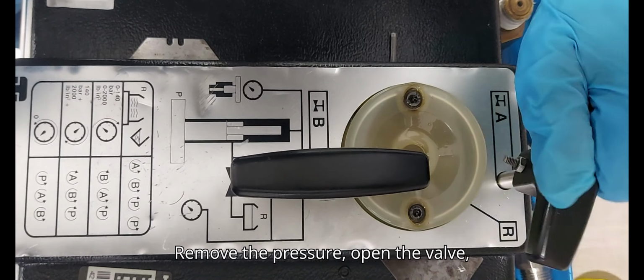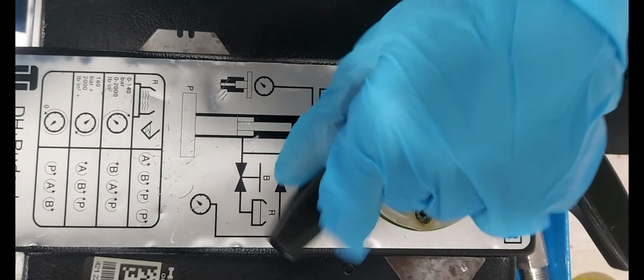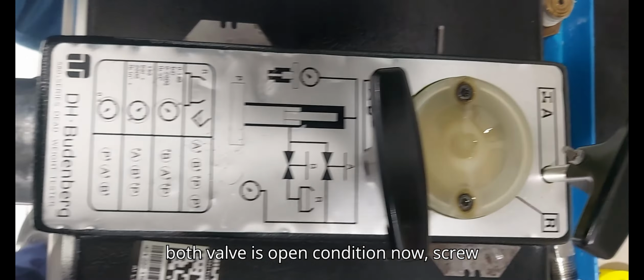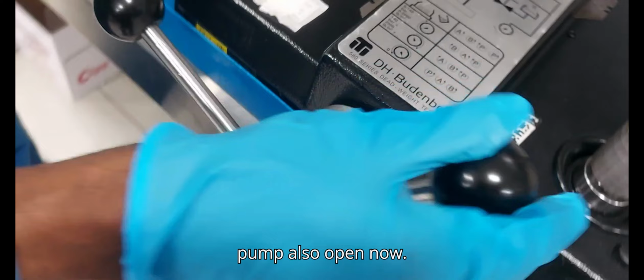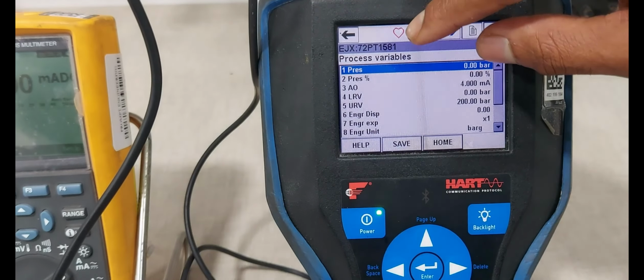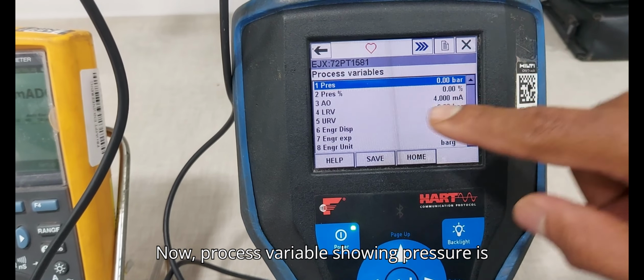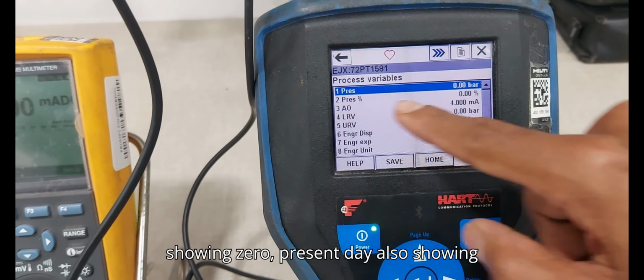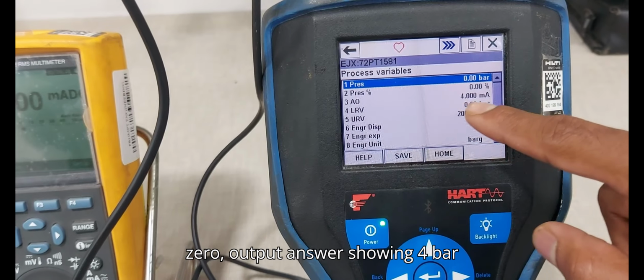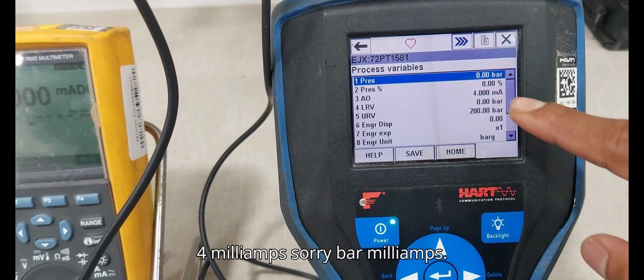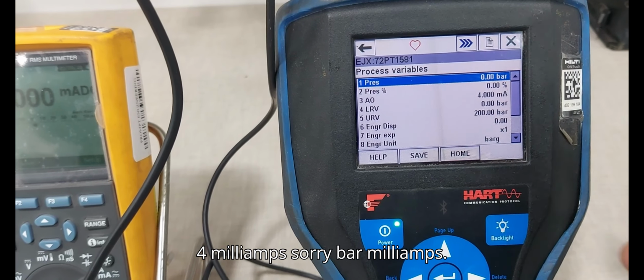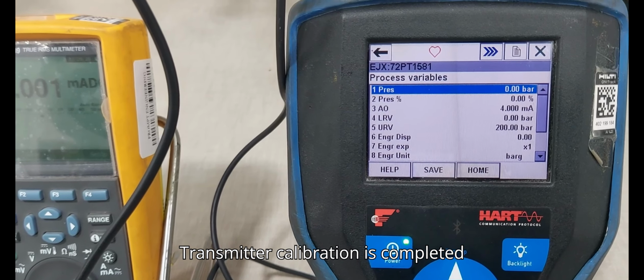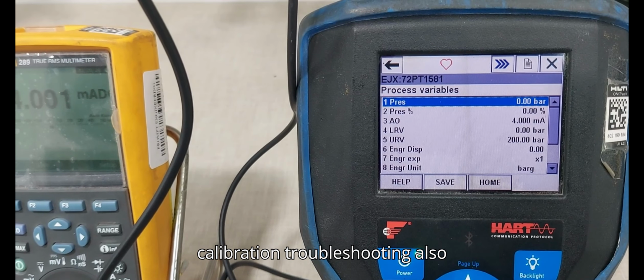Remove the pressure. Open the valve. Both valves are in open condition now. The screw pump is also open now. Now the process variable shows pressure 0, percentage also 0, output also 4 milliamps. Transmitter calibration is completed. Calibration troubleshooting also completed.